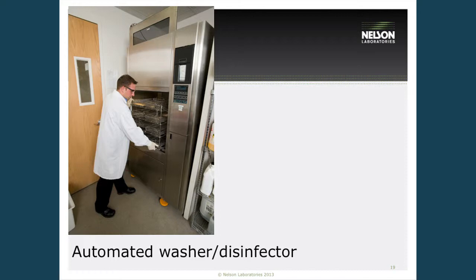Dried contamination also creates issues with microorganism testing, because organisms die off and you no longer have a starting titer to show you actually killed or removed the required amount. Regarding automated washer disinfectors, it's important to use standardized cycles — not just any soak and rinse — because central service personnel are loading devices and running standard cycles without choosing a specific cycle for each device type. We need to make sure those cycles are standardized.